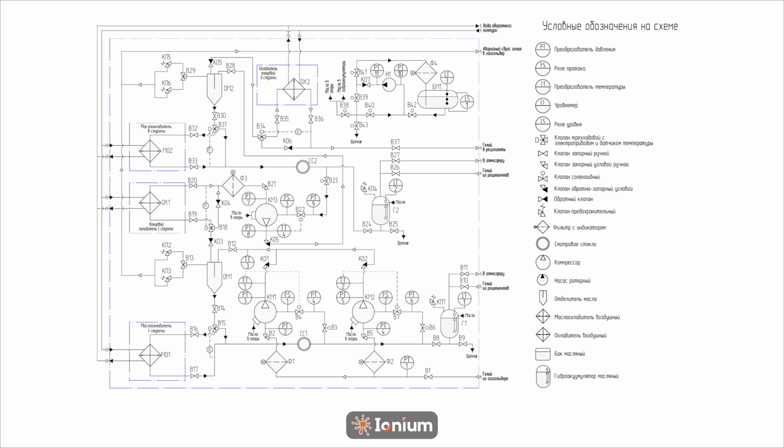All screw-type oil-filled helium compressors are classified as volume displacement devices with an open stuffing box design, where the lead screw shaft features an open cantilever and is connected to the motor's shaft through a flexible or another type of coupling. Excessive heating of machine components, such as elastic seals, intensifies helium leaks and reduces the overall efficiency of the compression process.